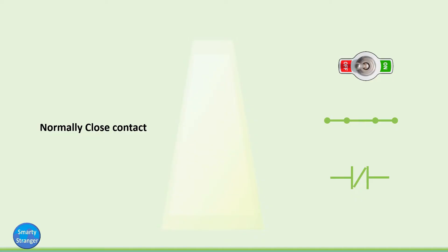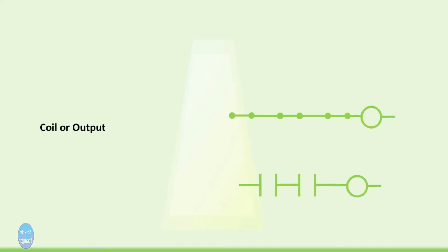The second symbol is the normally closed contact. Normally closed contact is like a closed switch. When its corresponding physical input is energized or high, the normally closed contact becomes an open contact. When the input is de-energized or low, it becomes closed again. Third is the coil or output. When all contacts in a rung fulfill the requirement, their related coil is energized. If any contact does not fulfill the requirement, the coil will not be energized.